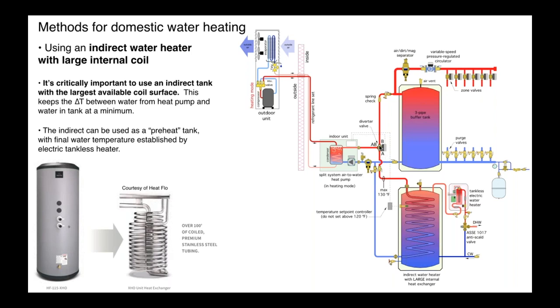Now, up above here, we just have a diverter valve. So basically the diverter valve, when the system calls for domestic water heating with some kind of a temperature set point control, would direct the flow coming off the heat pump condenser into the coil in the indirect tank. And the buffer tank just sits there. There could be energy in the buffer tank that could simultaneously be going out to the load. But obviously, if the load is taking heat from the buffer tank, the temperature is going to go down. And as soon as we satisfy the domestic tank, we're going to go back and bring the buffer tank temperature back up again. So basically, we have a prioritized domestic hot water scenario here from controls.